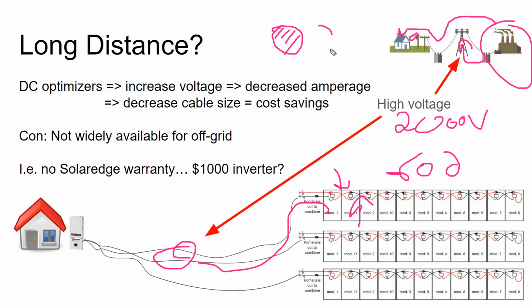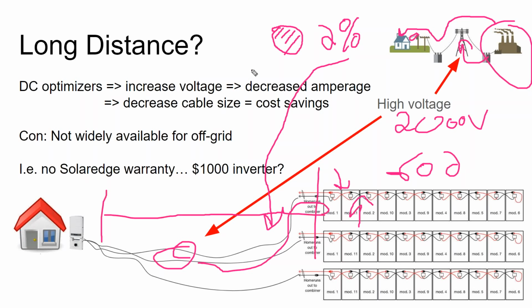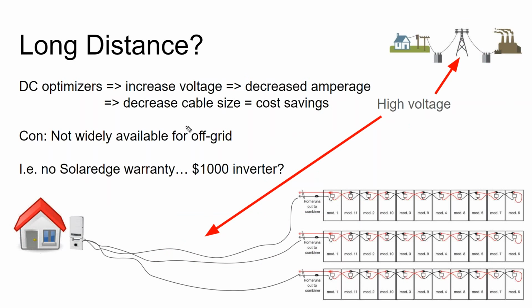But the problem is when you're sizing your cable for a 2% voltage drop and you have to upsize your cable because of the long distance between the array and the home, you end up using, you know, a 100 amp cable for what might be an 8 amp circuit because you need to upsize it. And that's a little extreme, but it's to make a point. You end up upsizing your cable for the voltage drop, and that means you end up having a lot more ampacity capability in that cable than what you're ever using. So you're overspending on your cable budget.